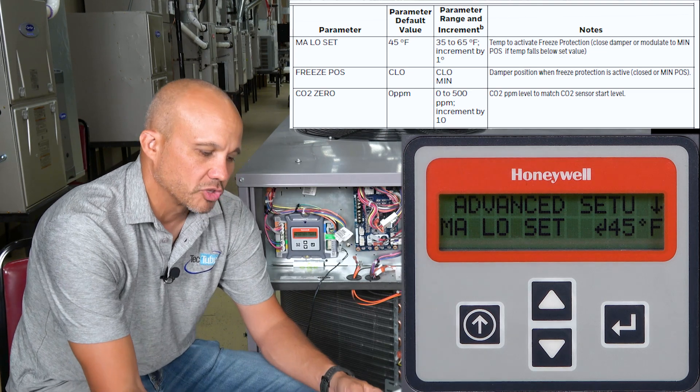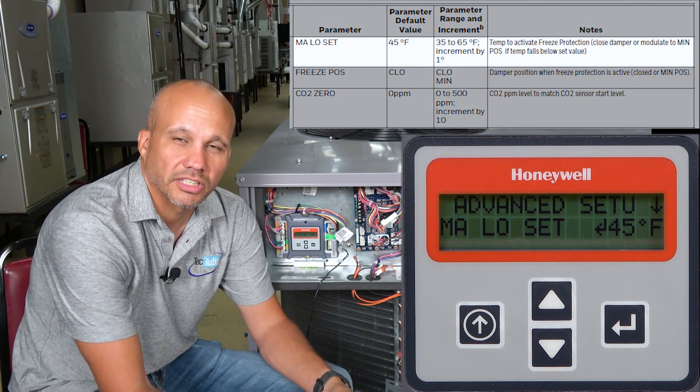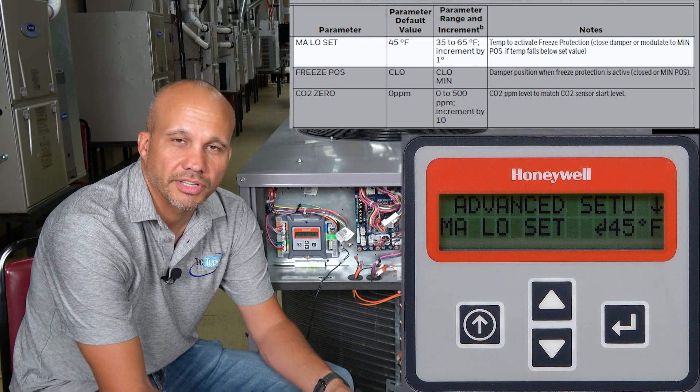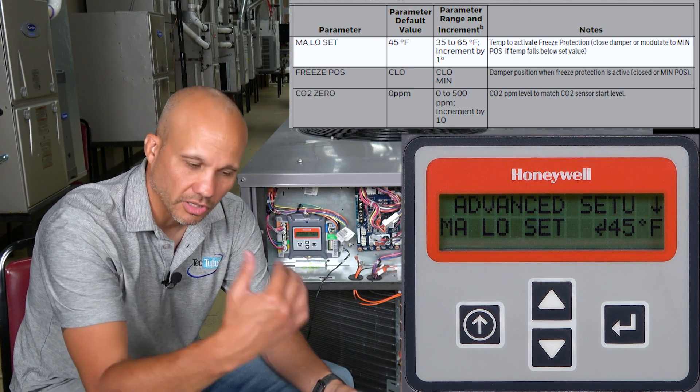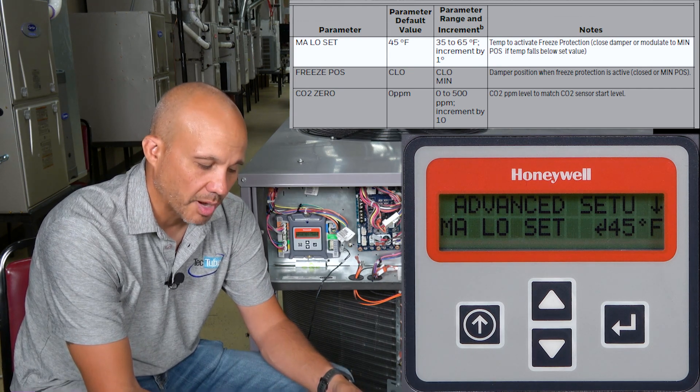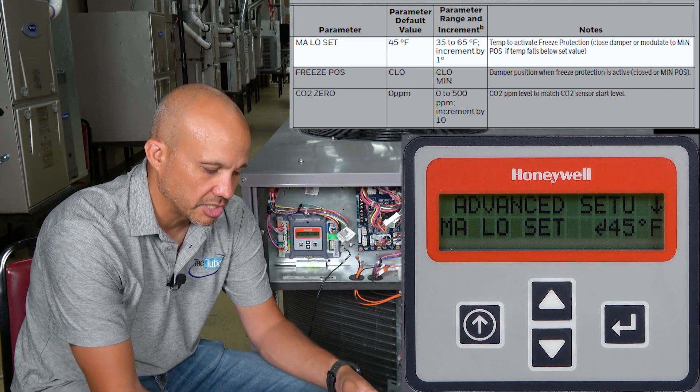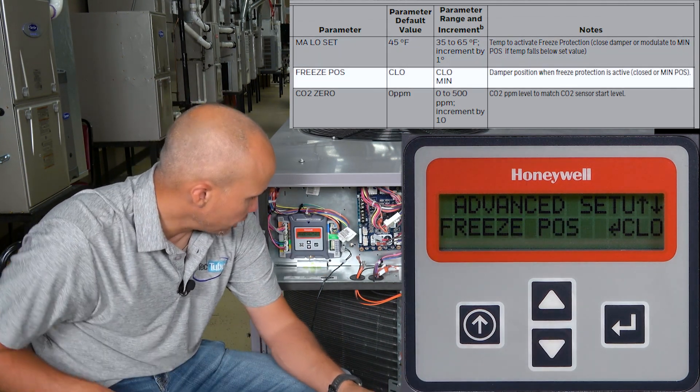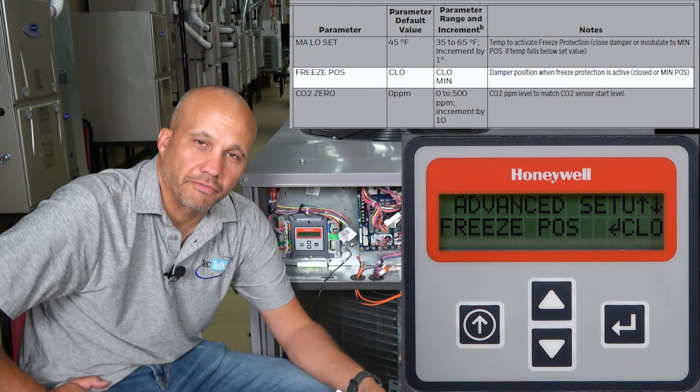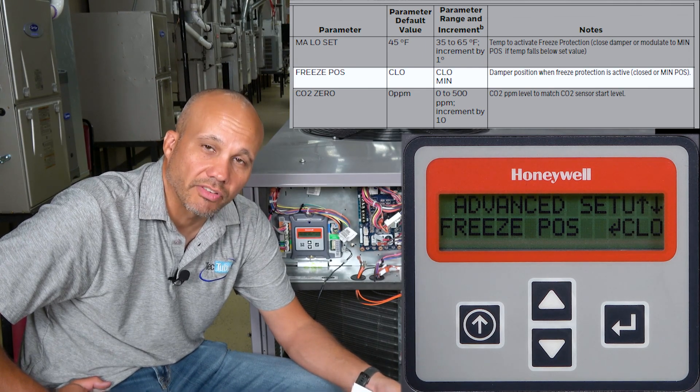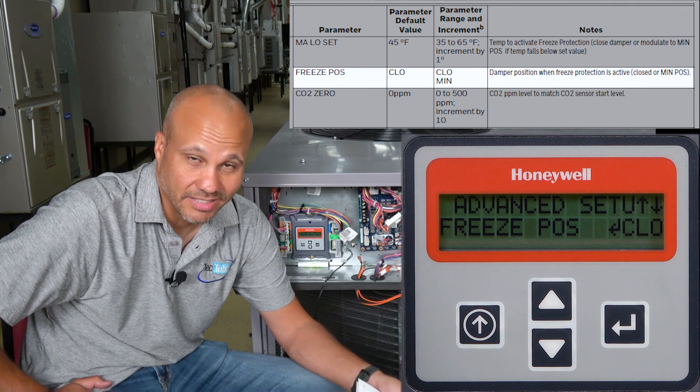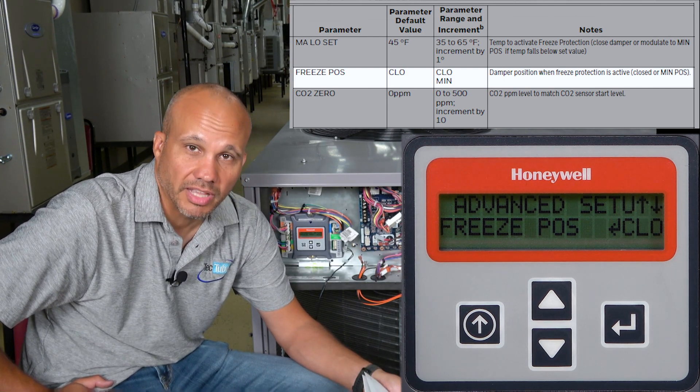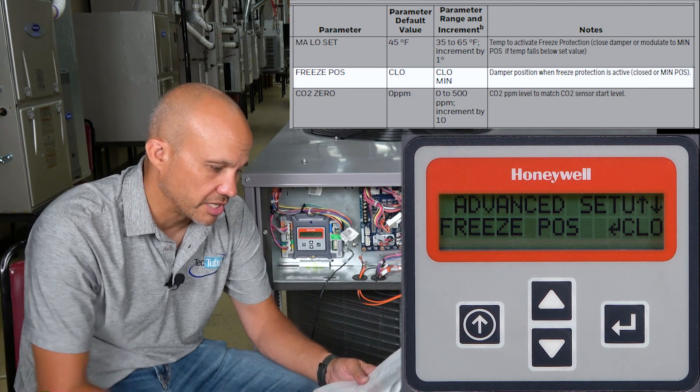The first one is mixed air temperature low limit. This is basically a mixed air temperature freeze stat. The default is 45 degrees. If it's below 45 degrees, it's going to assume there's a freeze condition and it's going to go ahead and start closing that damper off. That's probably a pretty decent number. If you scroll down one, freeze position close. So if I get below 45, close the damper. If you want to, you can have it go to the minimum when it's below 45.